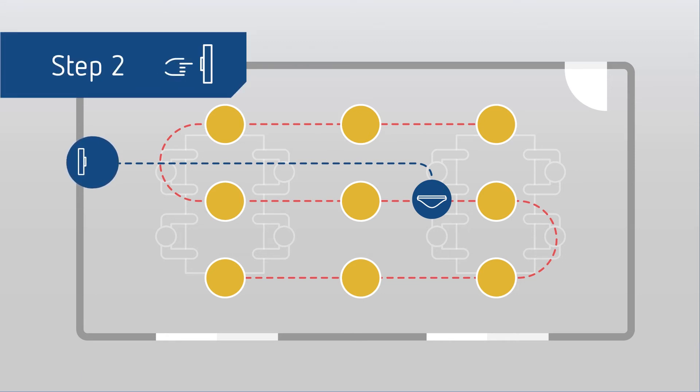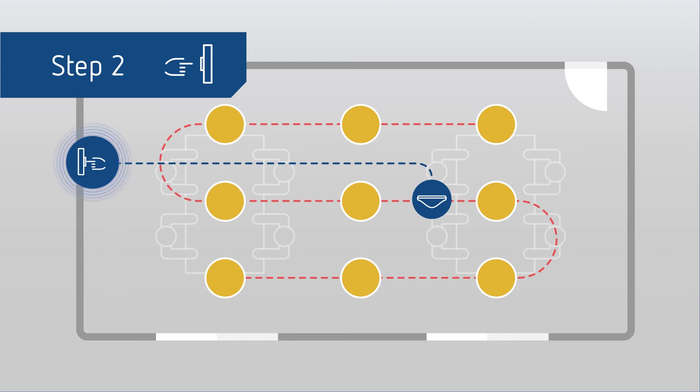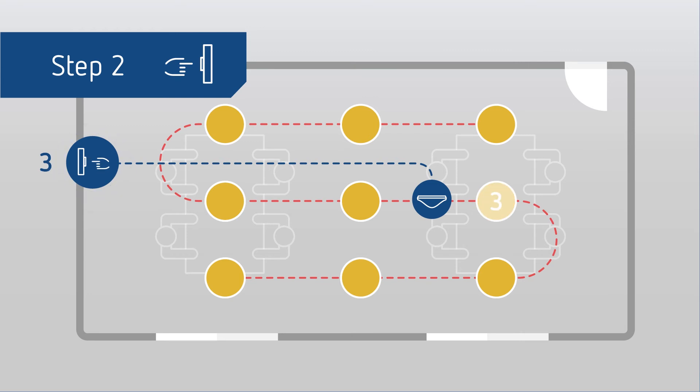The grouping process is started with five short presses and one long press of any connected switch. A DALI lamp starts to pulse. One press of the switch assigns it to group one, two to group two, and three to group three. The lamp confirms the assignment by dimming to 20%.